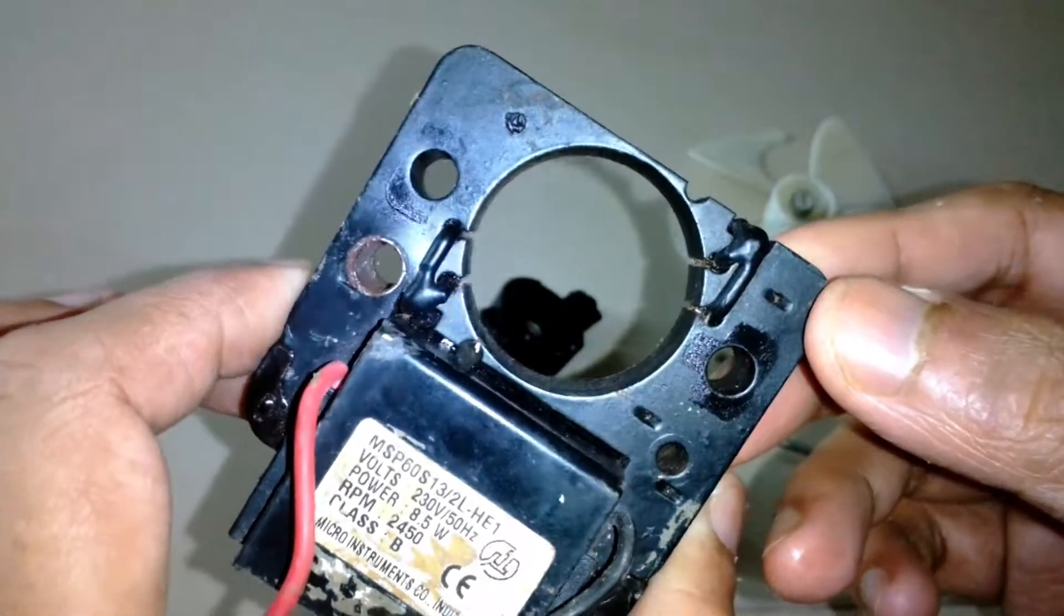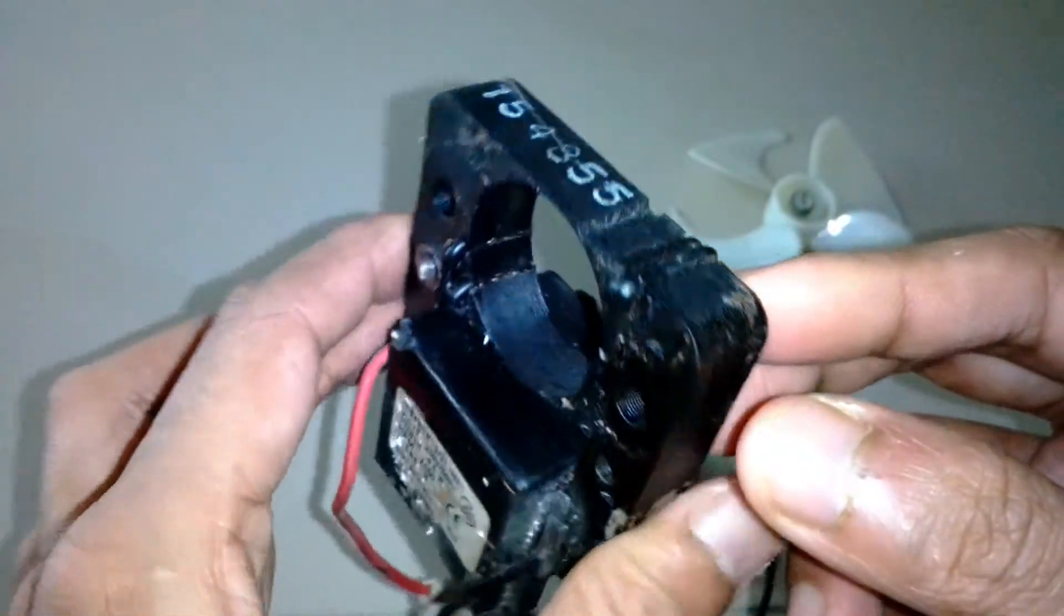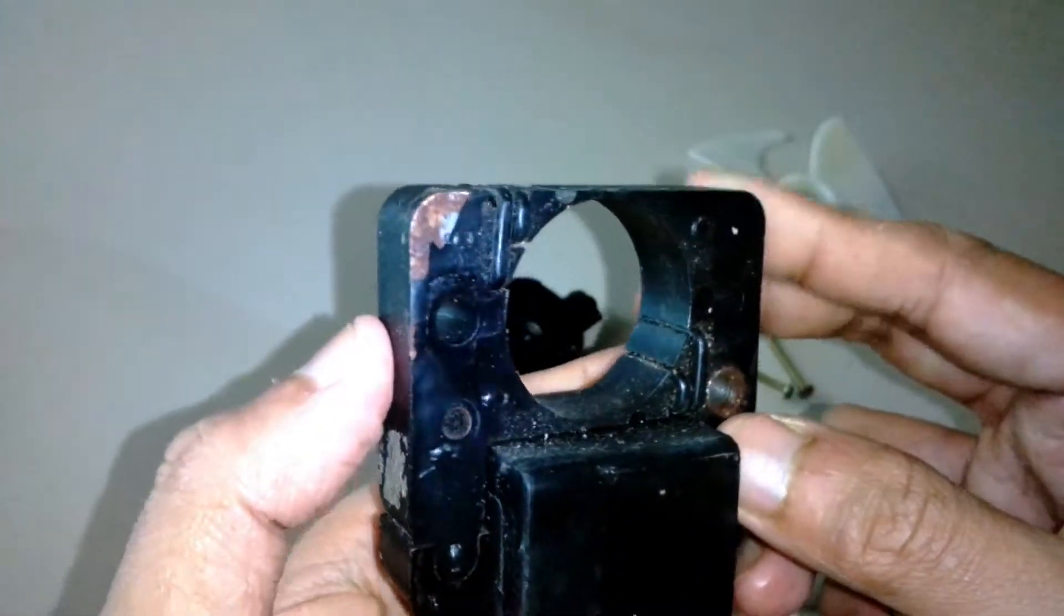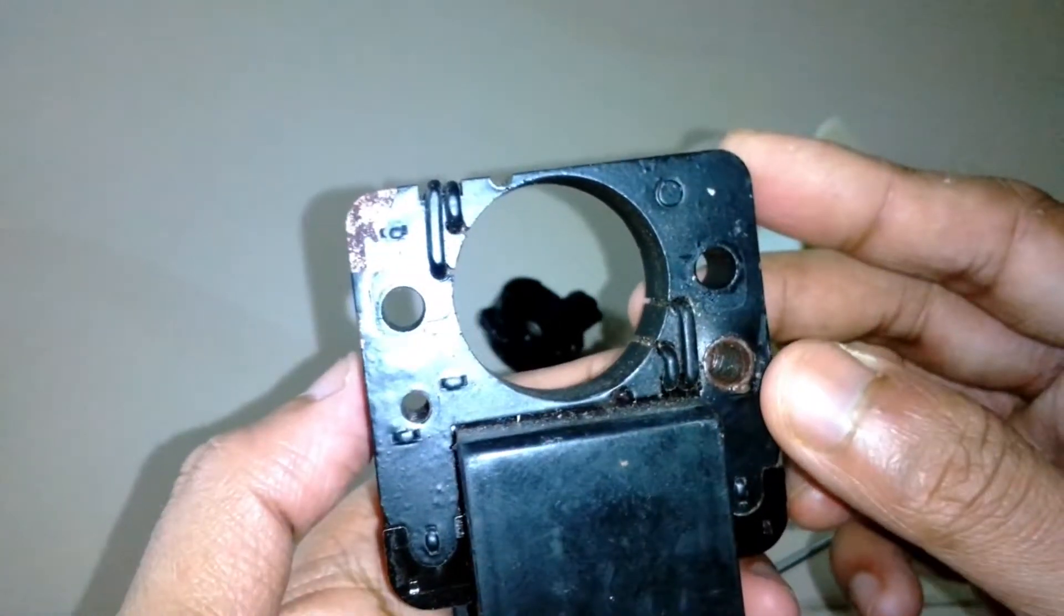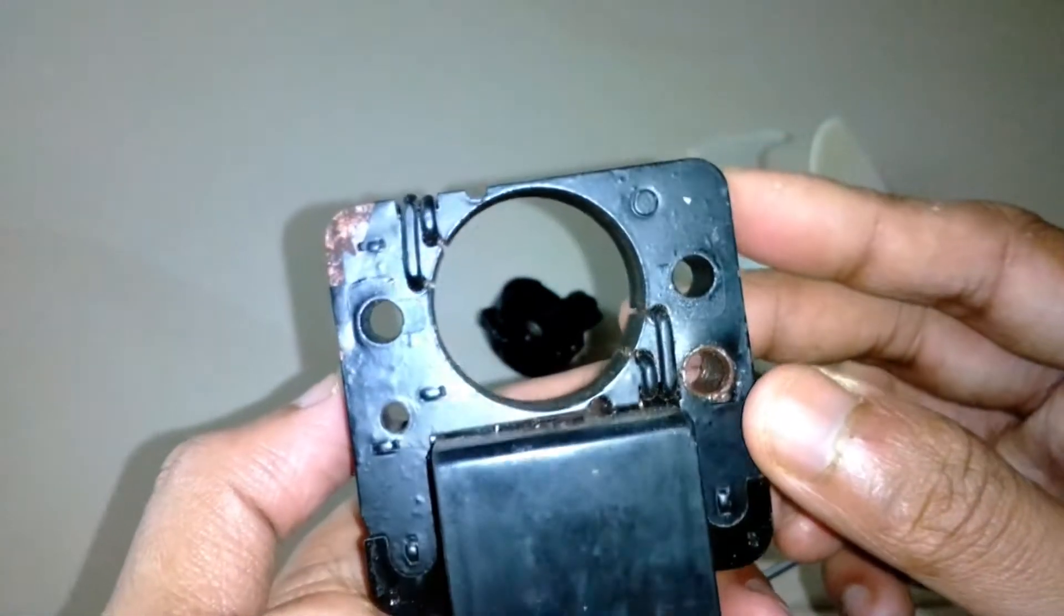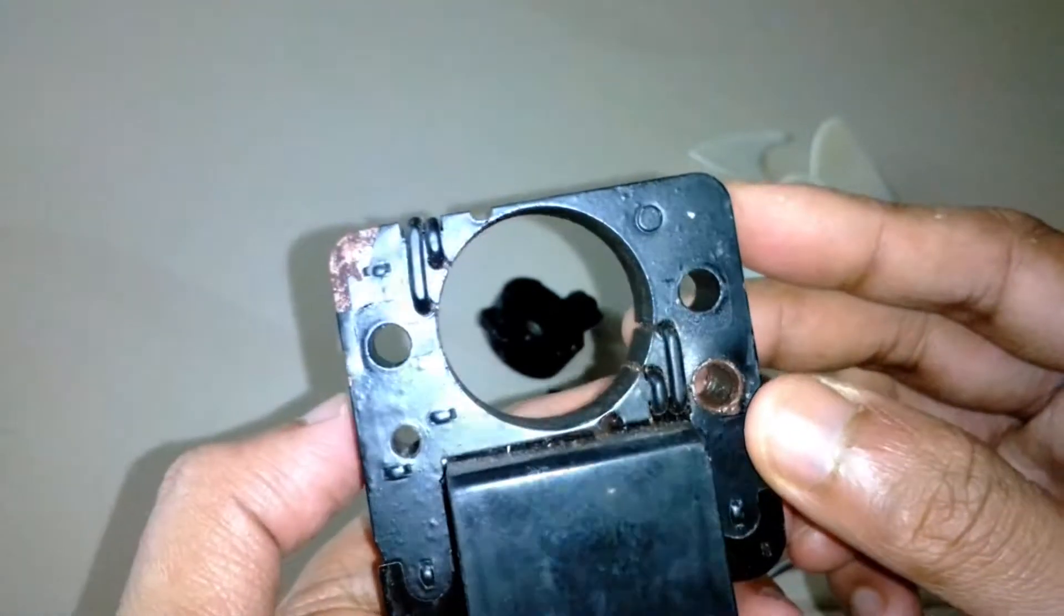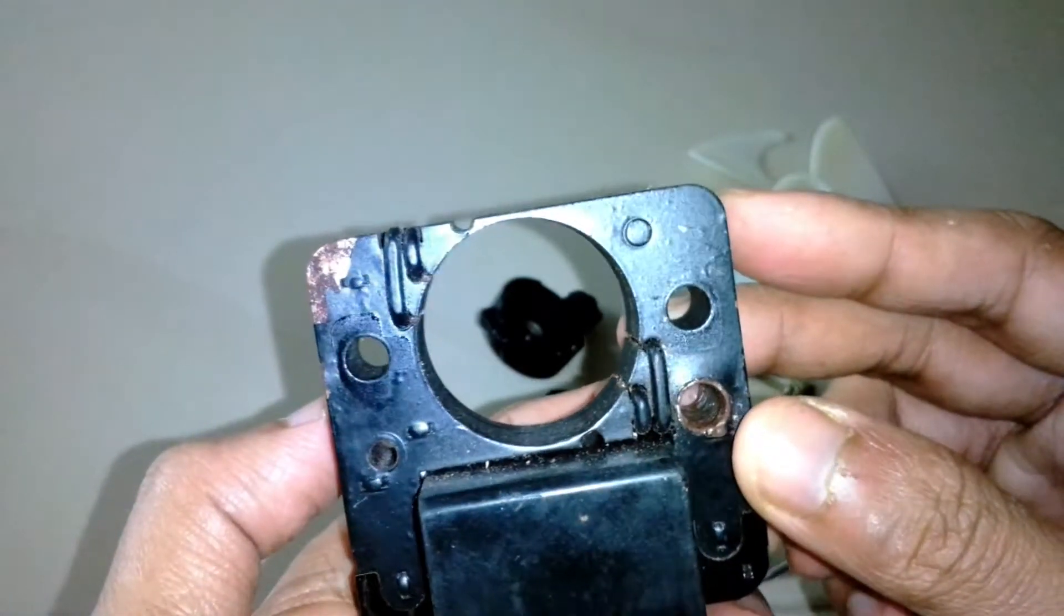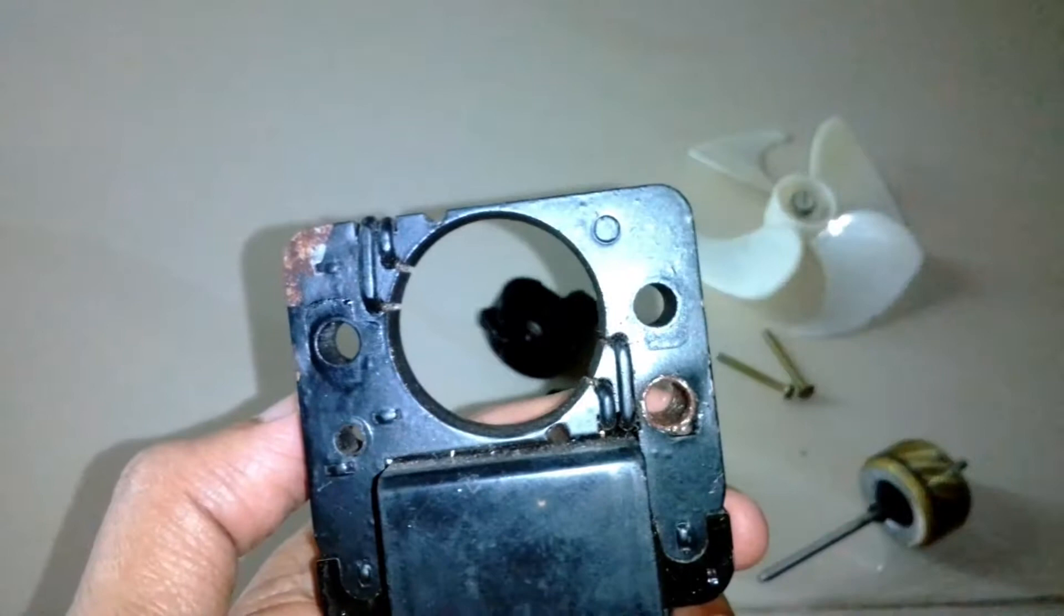In other types of motors, such as split phase induction motors, the phase shift is generated with a capacitor. Here the phase shift is generated with these copper rings, and that's why they're called shaded pole motors.